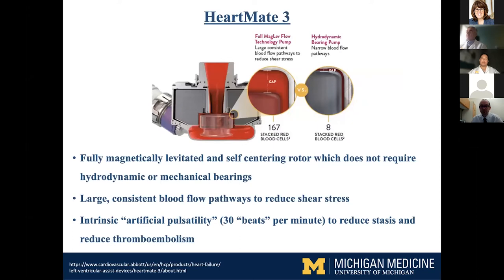About HeartMate 3 — that's the pump really available right now. It is fully magnetically levitated, so even if it's not rotating, it will just float statically inside the pump housing. It's got a self-centering rotor that doesn't require contact with anything — there's no mechanical bearing and it's not dependent on blood to lubricate the mechanism. It's not hydrodynamic. It has very large gaps that allow blood to travel and promote laminar flow, reducing heating compared to smaller gaps in the prior hydrodynamic pump, which still had some thrombosis and stroke issues.